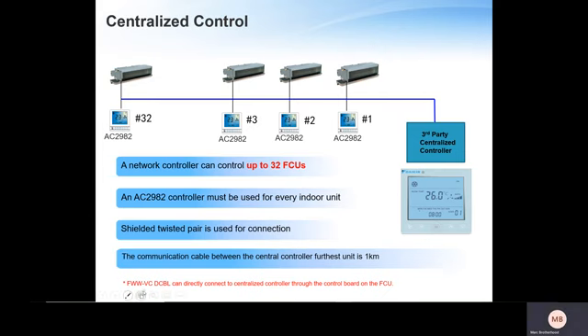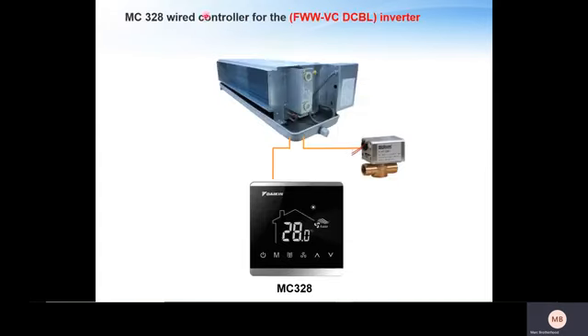If going for the FWW-VC, which is the fully inverter unit, then the BMS control can be connected straight to the control board on the fan coil unit. You don't necessarily need a remote to link the RS485 network into per fan coil unit. If we go for the inverter model, you would require this LCD controller. And here you can also see we can offer valve control, but this is also all control of the circuit board of the unit.